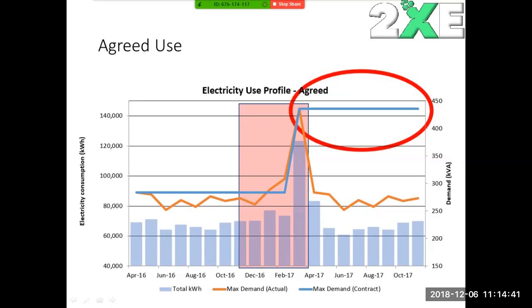Then something happened in March and they had a humongous peak, which basically doubled their electricity demand during this stage. We're talking about an increase of about $20,000 to $25,000 during this time, from just an exceedance of a couple of short minutes. And that's the demand they're set at for the next 12 months.